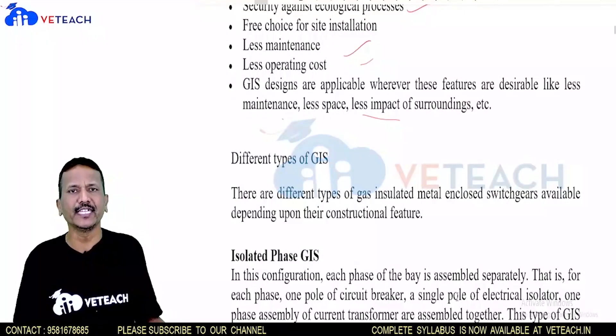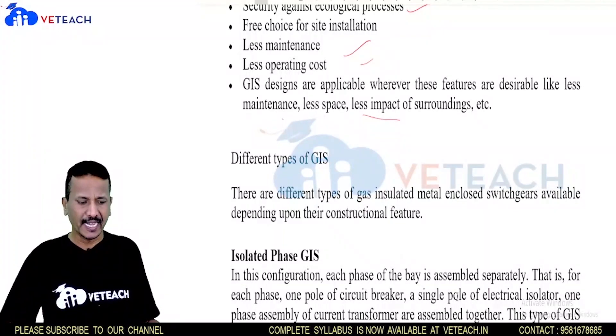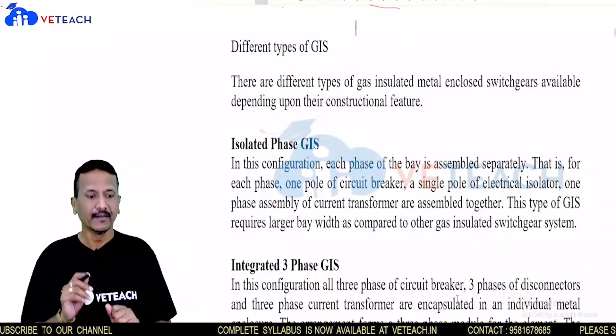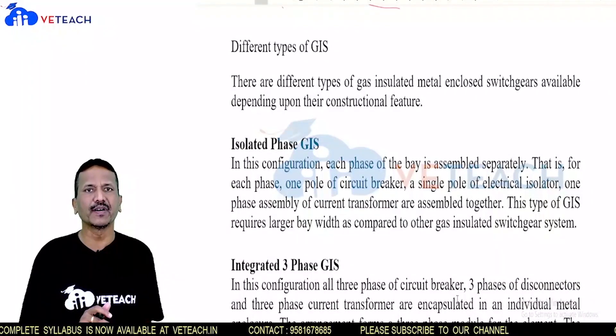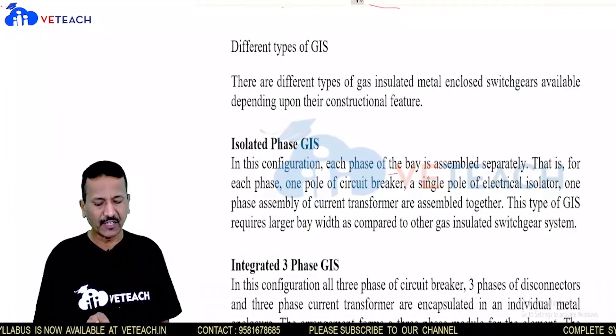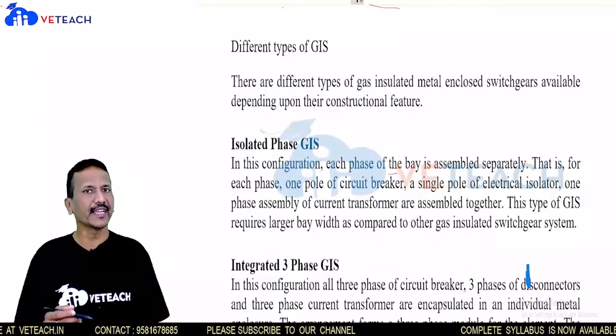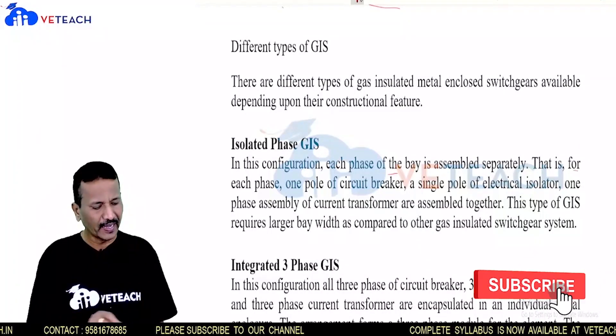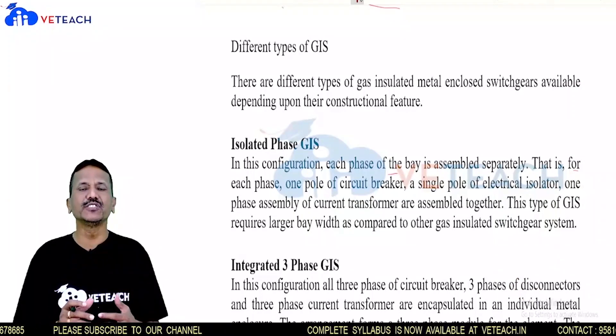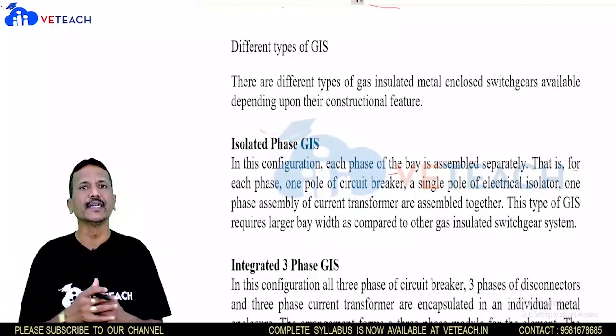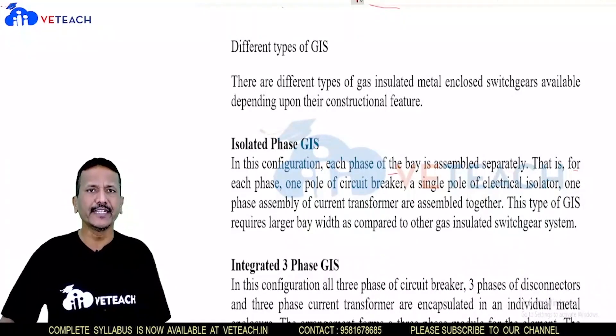There are different types of GIS. The first is isolated phase GIS, which is a newer technique. In this type, each phase of a bay — where two incoming/outgoing lines connect — uses one pole of a circuit breaker, a single pole of an electrical isolator, and one phase of a current transformer. This is called a single system or isolated phase GIS.